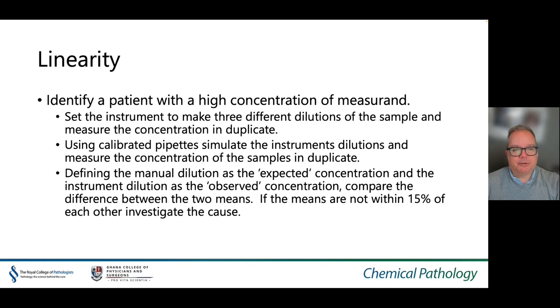The procedure for linearity testing is as follows: identify a patient with a high concentration of the measurand, set the instrument to make three different dilutions of the sample and measure the concentration in duplicate for those three diluted points. Using calibrated pipettes, simulate the instrument's dilutions and measure the concentration of the samples in duplicate. Defining the manual dilution as the expected concentration and the instrument dilution as the observed concentration, compare the difference between the two means. If the means are not within 15% of each other, investigate the cause.